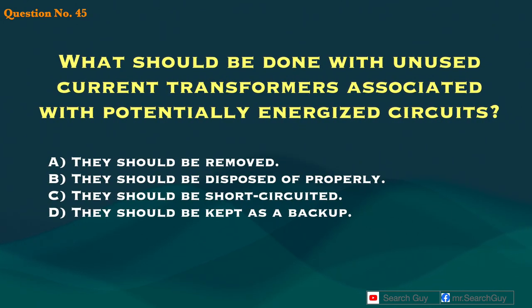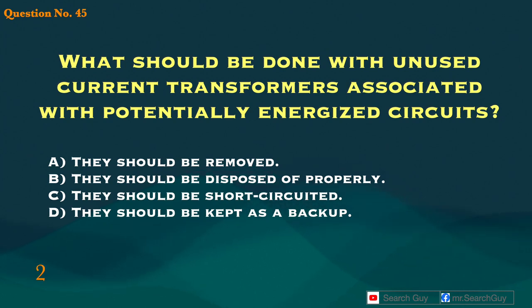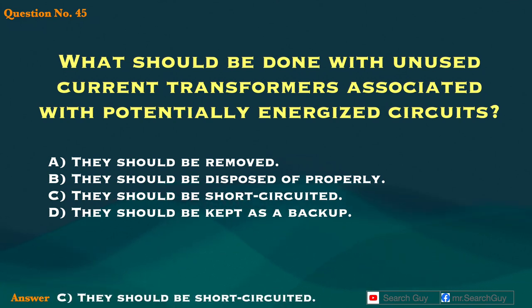Question 45. What should be done with unused current transformers associated with potentially energized circuits? A. They should be removed. B. They should be disposed of properly. C. They should be short circuited. D. They should be kept as a backup. Answer: C. They should be short circuited.